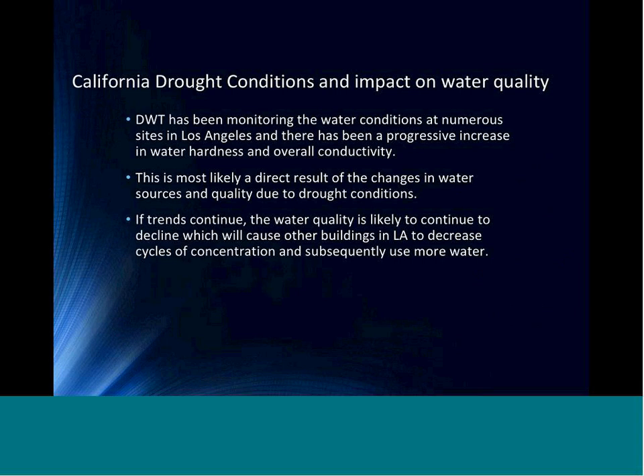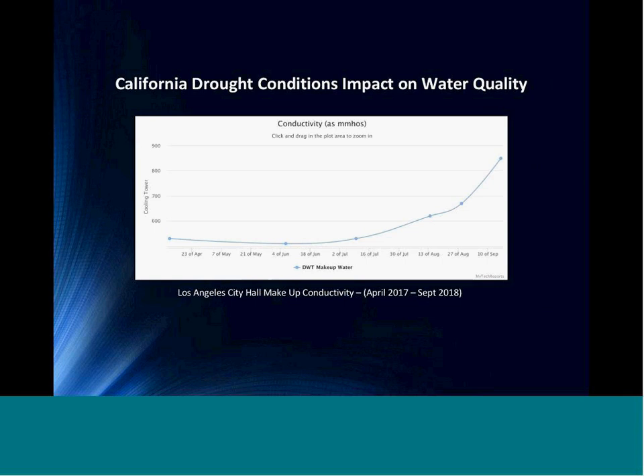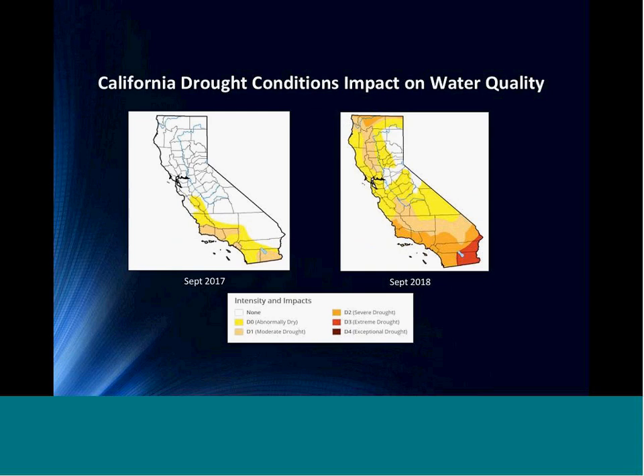I want to just mention, the drought conditions that we have seen in California are ongoing, and I have been looking at quite interesting trends that we're seeing in this process. If you go to the next slide, since we started our analysis of the building, this is a graph of the conductivity that we've recorded in the process, and as you see, it's had a dramatic upswing. It seems that it's continuing on this path, and past this point, we're seeing some dramatic fluctuations that are quite unusual. I don't know for certain that this is a direct indication of instability in the makeup water, but we've seen that in other markets where once you reach a certain saturation point, you get dramatic instability in some of the silica and the overall hardness of the water. Next slide.